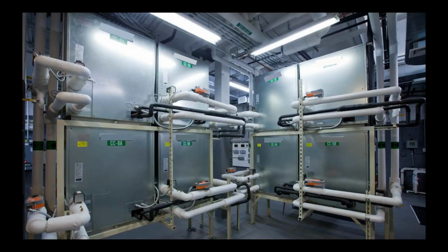We're connecting VRF to the ground loop. So it's indoors. It's a water to refrigerant heat pump system, and each of those modules, those silver boxes stacked one on top of the other, is about 7 or 8 tons. So in the space of a stacked washer dryer, you can get 14 tons of heating and cooling, and it's all accessible indoors from a maintenance standpoint.